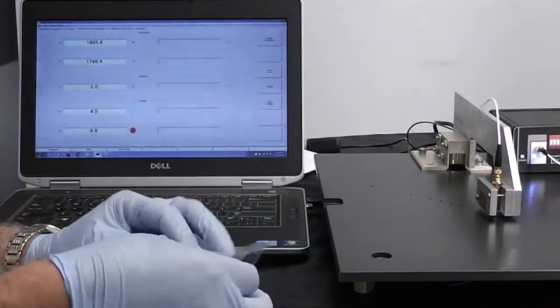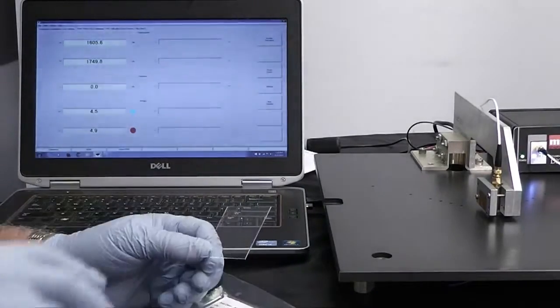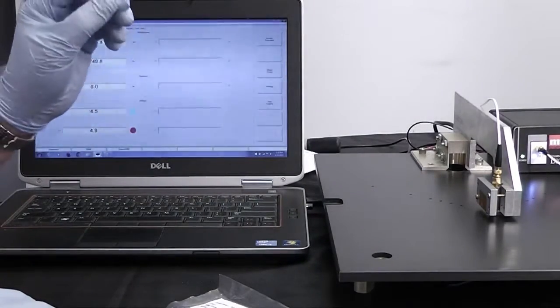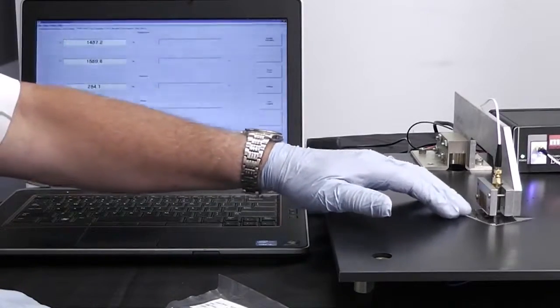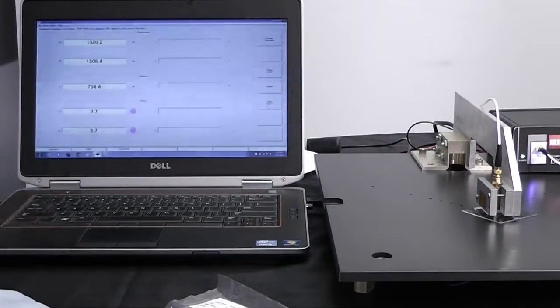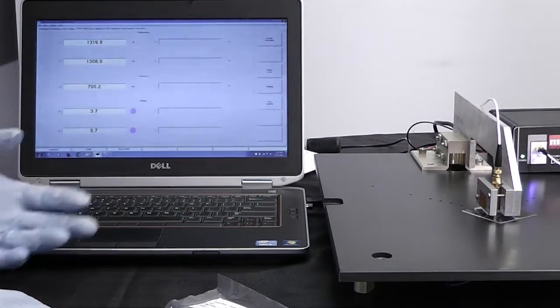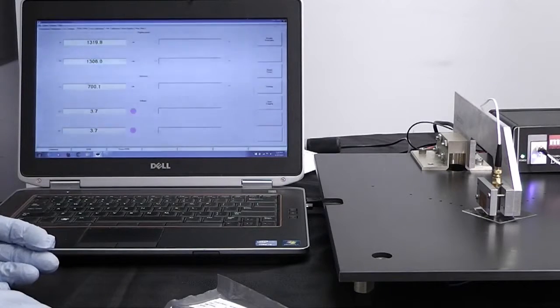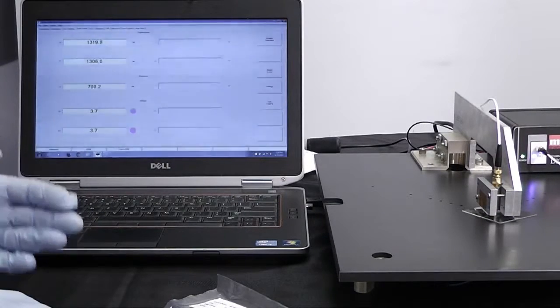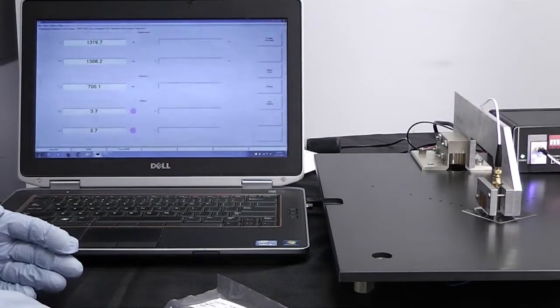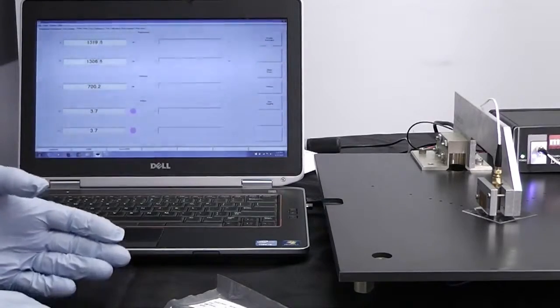So I've already set up the slope factor. I've checked it before. What we do is we put the first sample under here, and we've entered that sample thickness in here, and then calibrated on that. So every time you start with the known slope factor and a sample, you have to calibrate the sample to the system, and that's fairly easy to do.